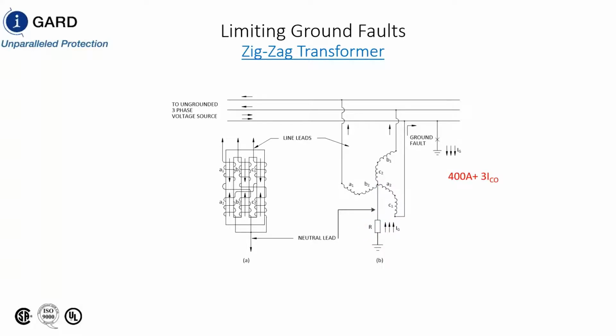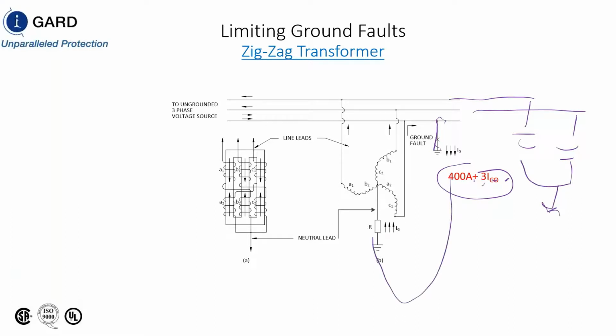So if you limit the fault current to 400 amps, and I've had this conversation with many people, at the point of the fault, your fault current is going to be equal to 400 amps plus the charging current. The charging current does not return back through the resistor. That charging current returns back through the capacitance of the unfaulted phases because they're connected to ground. Only through the resistor do you get the 400 amps. So you get 400 amps coming back through the resistor.